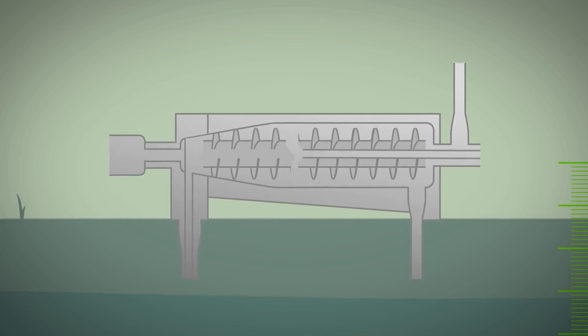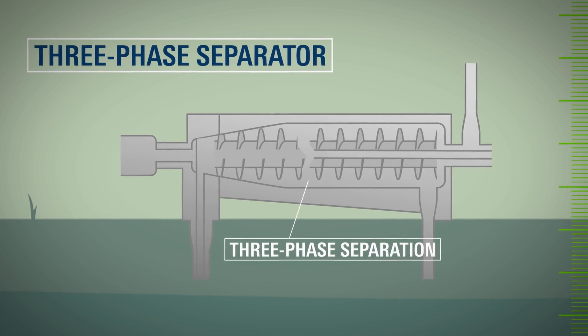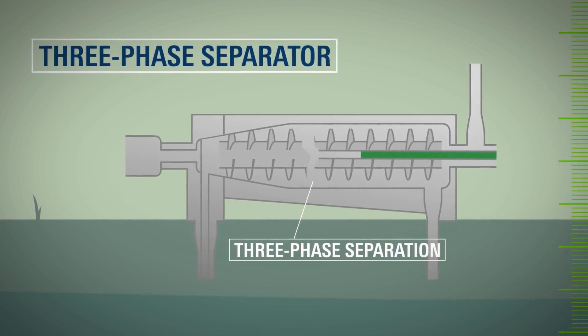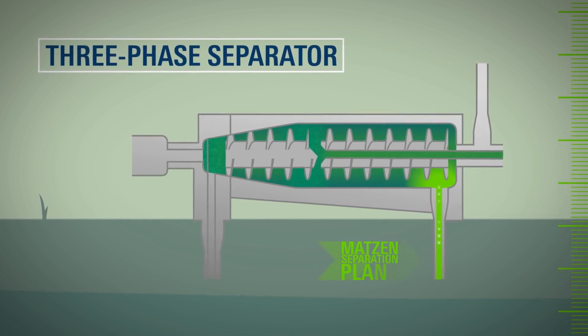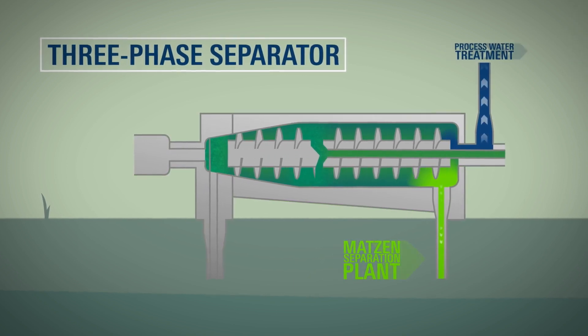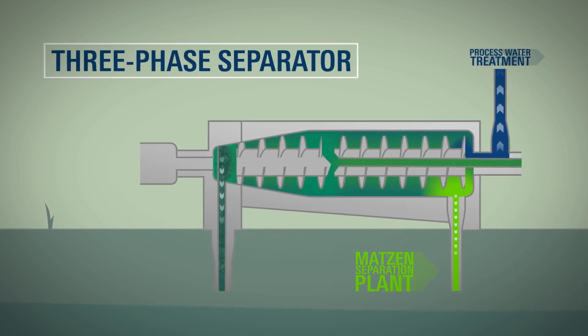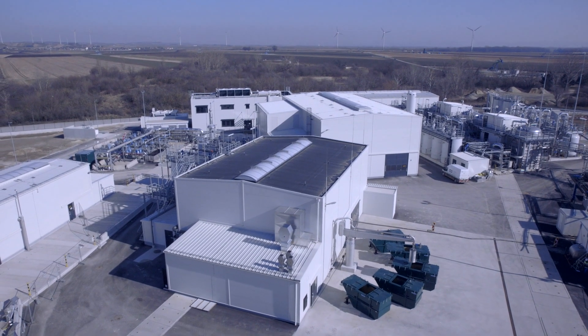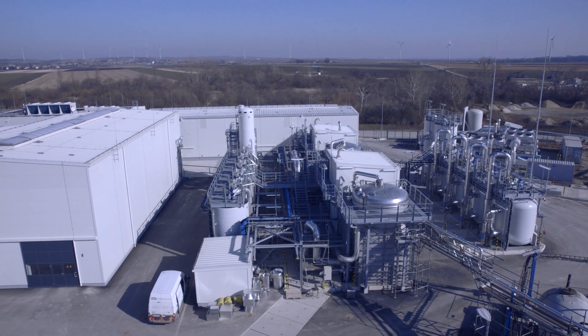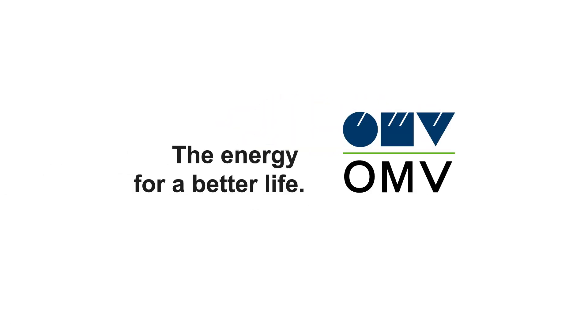Now the final step in the sludge treatment procedure: three-phase separation. The heated sludge mixed with additives arrives in a three-phase separator, which divides the sludge into its constituent parts using centrifugal force. The oil, water and solids are then piped off separately. The oil is transported back to the Matzen separation plant, and the accruing water is pumped back to the process water treatment plant. All that is left is the solid material which, rather than being dumped as is typical, is sent to an external facility for thermal recycling. Through its investment in the new Schoenkirchen water treatment plant, OMV once again demonstrates that it is a reliable and environmentally conscious partner of the region.